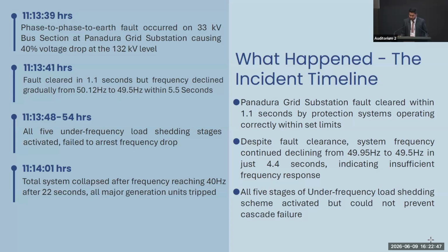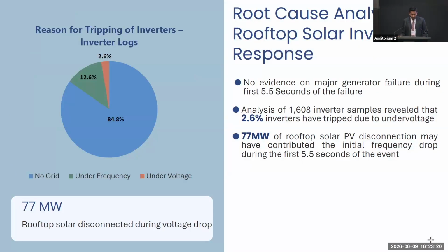Despite the fault clearance, system frequency dropped to 49.5 Hz from 50 Hz within 4.4 seconds, indicating insufficient frequency response. Then all 5 stages of the under-frequency load shedding scheme activated, and it led to a cascade failure. Finally, the total system collapsed within 22 seconds once the system frequency reached 40 Hz. The frequency continued to decline to 49.5 Hz from 50 Hz within 4.4 seconds even after clearing the fault, and we didn't find any evidence of any major generation failure which caused this frequency drop.